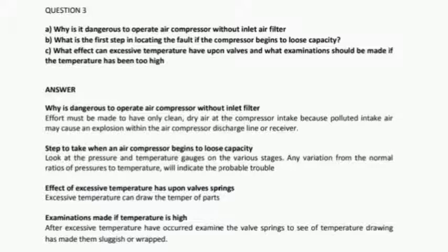Some examinations made if there is high temperature may include the following. Examine the valve spring to see if the high temperature has made it sluggish or weak. Examine the valve seat for carbon accumulation. Examine the valve generally for wear and carry out a valve overhaul to bring the valve back to normal working condition.